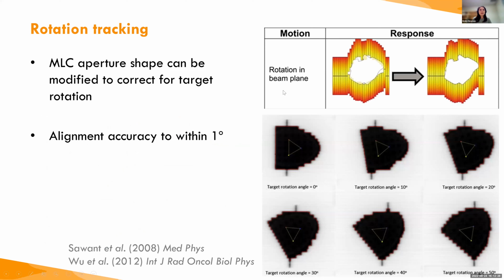So we can use MLC tracking to adapt to this rotation. If we have a motion signal in real time that's giving us six degrees of freedom information, we can correct for both rotation in addition to translation using our MLC leaves. I have an illustration here of how rotational MLC tracking works. Essentially, when we plan a treatment, we have a certain aperture shape. We can determine this shape, rotate it by the amount of rotation that we've observed in the target, and then calculate the MLC leaf positions that will give us this rotated shape.